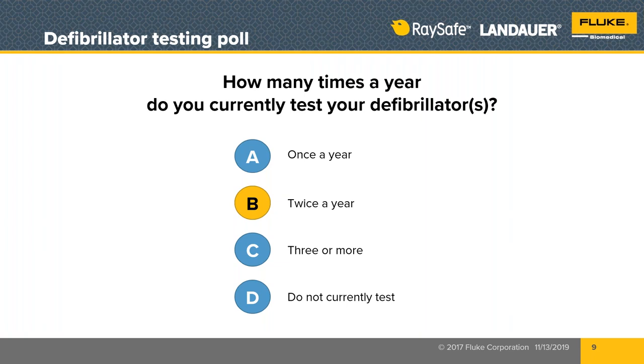Now, to be sure, there are a couple of medical device of defibrillator manufacturers that have set their frequency of inspection at once per year. But I'm sure you'll agree, when we looked at that 72,000 incidents since 2005, once per year is not enough. And so typically twice per year is pretty good. And it's about this twice per year is what we would look at for other kinds of life support devices and critical devices in the hospital. So we're sticking with the recommendation of twice per year.